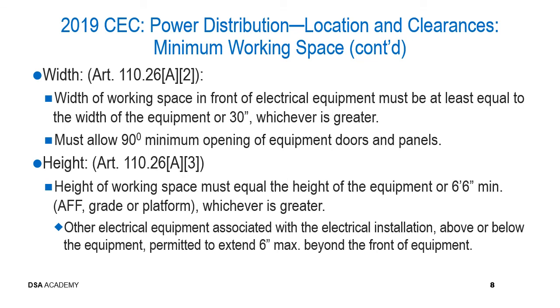Continuing with the minimum working space, the width of the working space in front of power distribution panels and electrical panels is identified in Article 110.26(A)(2). The width of the working space in front of the electrical equipment must be at least equal to the width of the equipment or 30 inches, whichever is greater. The working width must also allow a 90-degree minimum opening of equipment doors and panels. The minimum height of the working space in front of these power distribution panels must be equal to the height of the equipment or 6 foot 6 inches minimum above finished floor, grade, or platform, whichever is greater.